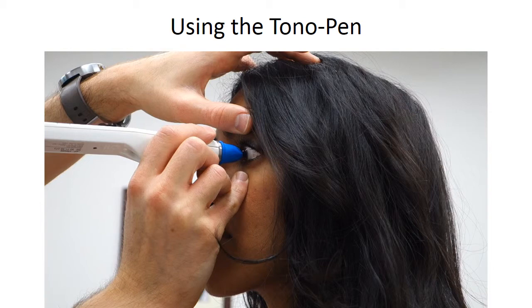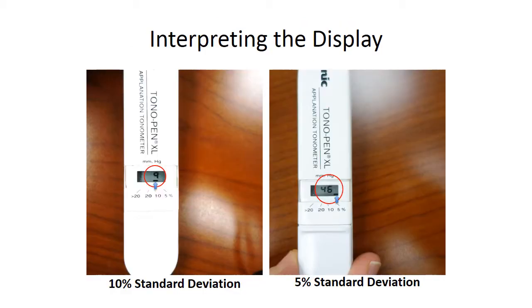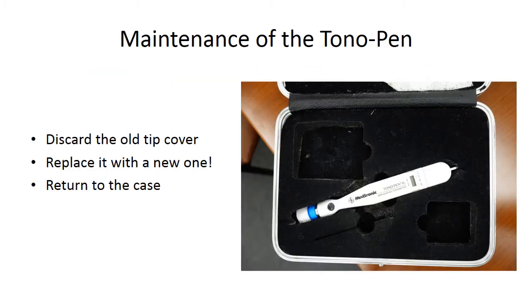A chirp will sound every time a valid reading is obtained. After several readings, a final beep will sound and the averaged IOP measurement will appear on the display. A single IOP number will be shown — this is the average. In addition, a horizontal bar will appear above one of four numbers below the readout, indicating the statistical reliability of the average measurement. If the bar appears above the number 10, the standard deviation is 10% or less of the number shown. If the display indicates a standard deviation greater than 5, you may want to repeat the measurement. Do the same for the other eye. When finished, throw out the used tip cover and replace it with a new one before returning the tono pen to its case.